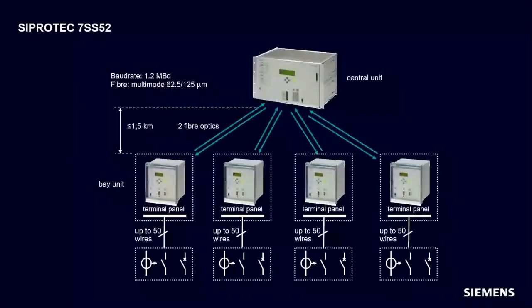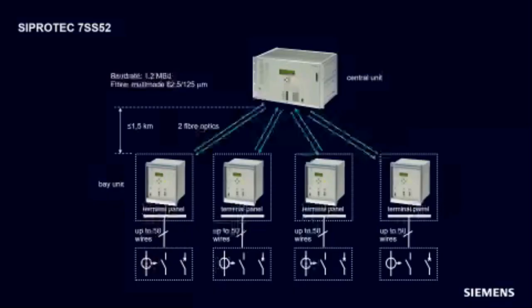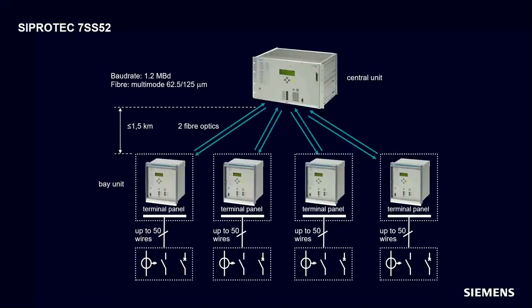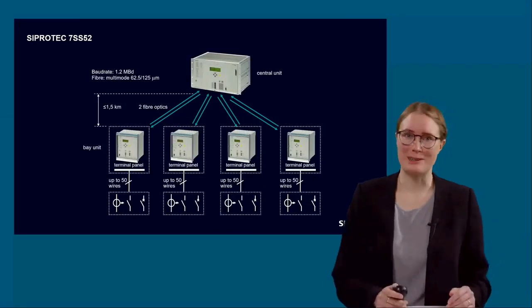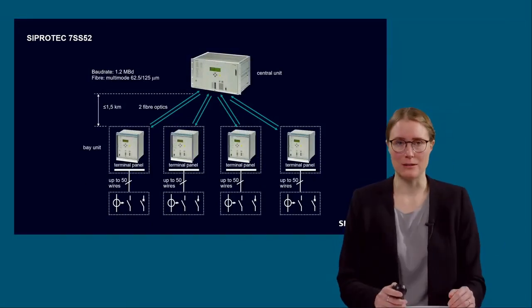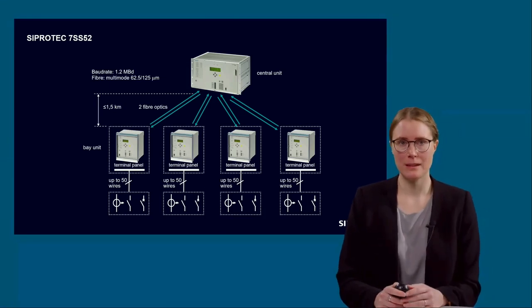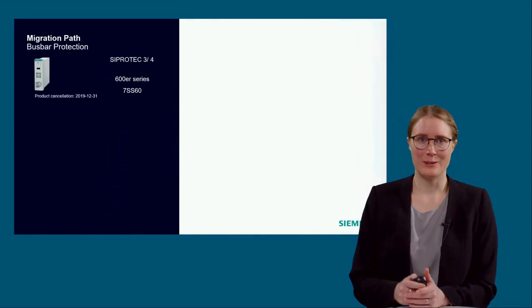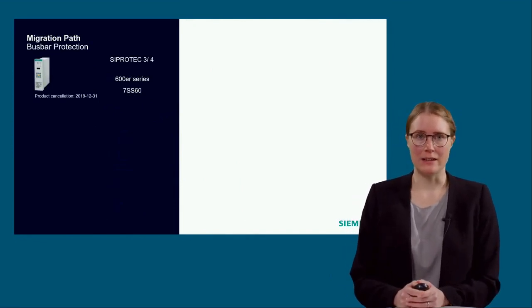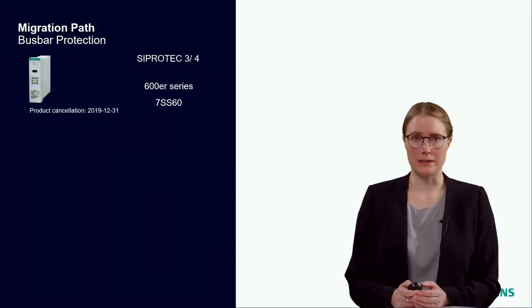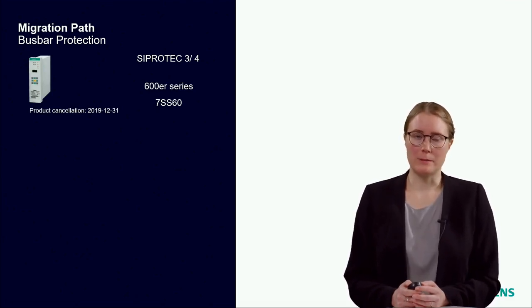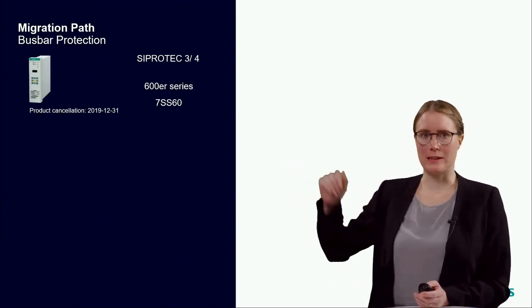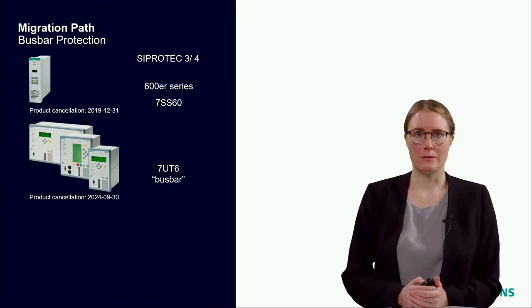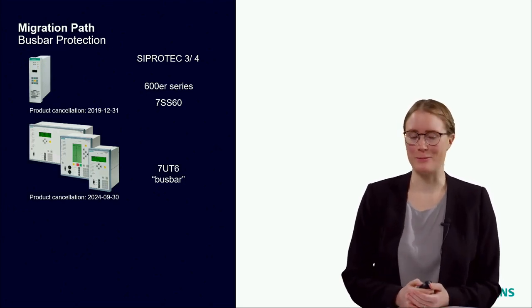The 7SS52 busbar protection is applicable for big substations with single, double, triple, or quadruple busbar systems, with or without transfer bus, with up to 48 bays and 12 busbar sections. In addition to the 7SS52 device, there are also other solutions in the SIPROTEC 3 or SIPROTEC 4 portfolio. With the SIPROTEC 3 portfolio, we had the 7SS60 device, which was a centralized busbar protection. This is the first device on the slide. Of course, the device is quite old, nothing we want to promote here.